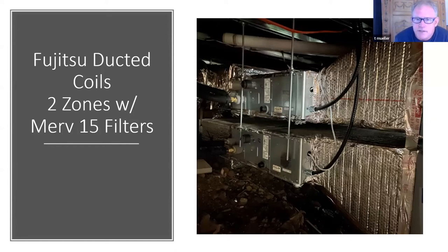The advantage to this is trying to reuse some of the existing ductwork, not so much the ductwork in the crawl space - we usually end up replacing all of the ductwork that's accessible. But all of our existing buildings have ductwork in the walls and floors that's hard to get to sometimes. So this is a way to reuse some of that ductwork and register locations while still transitioning to an electric mini split system.